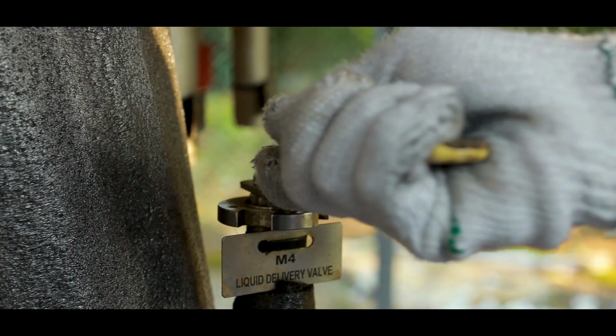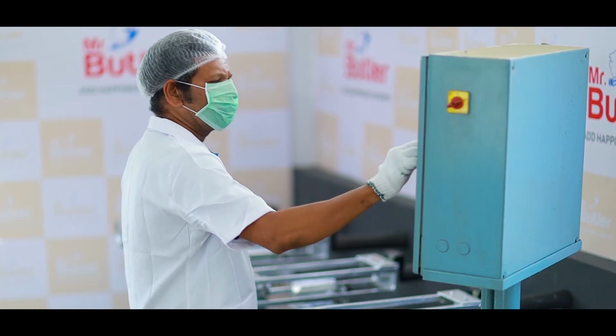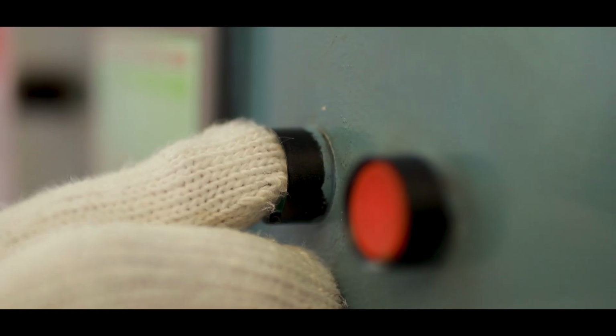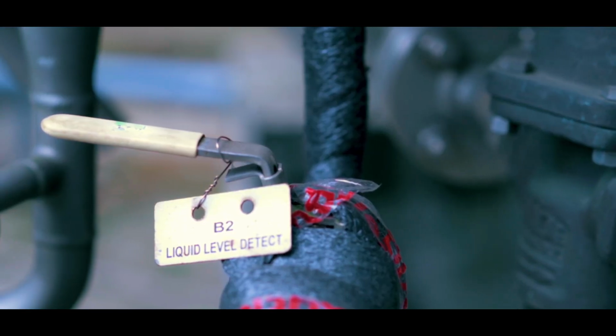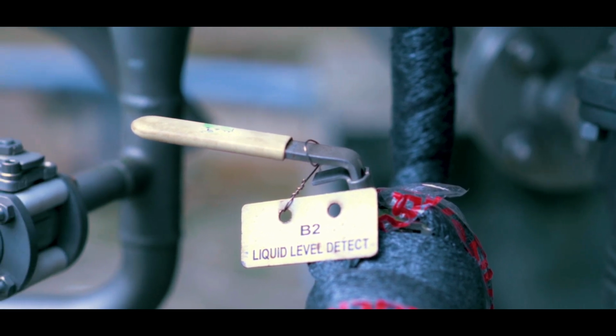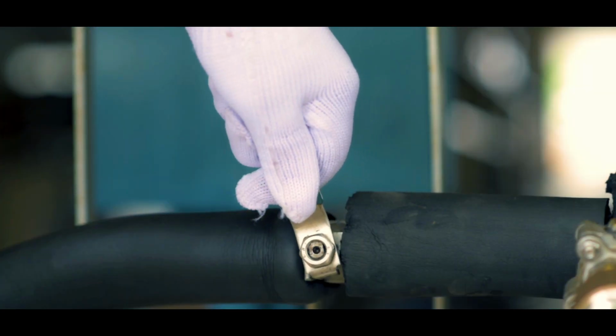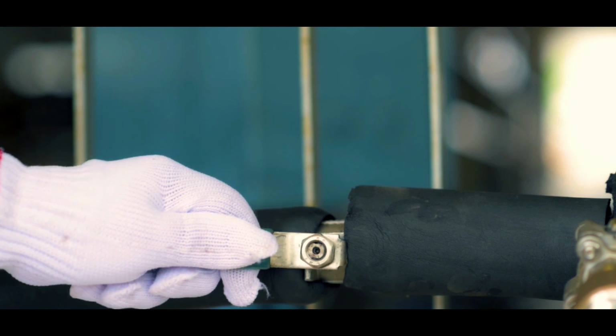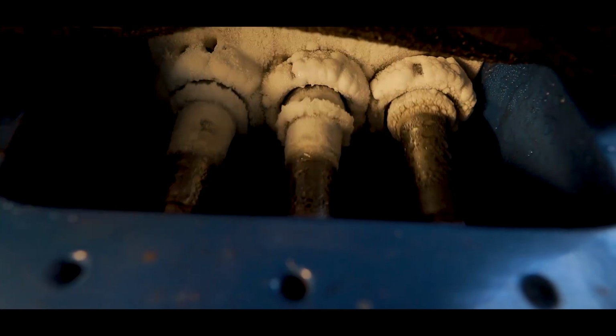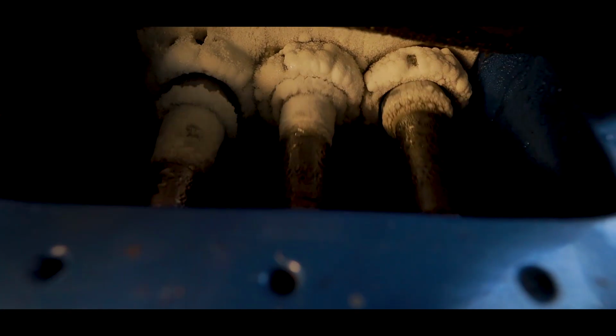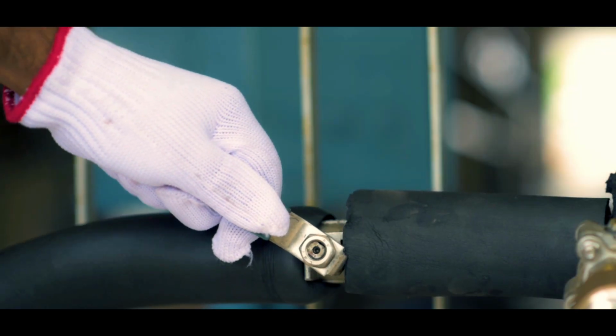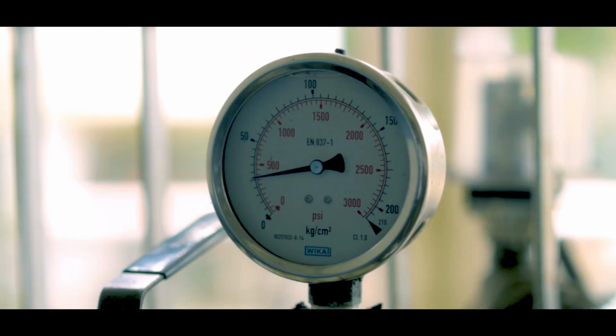First, open the input valve on the tank. Now, start the pump. After that, open the return valve on the tank and then open the bypass valve in the line. Now, the cool cycle starts. Run it for 5 minutes and then close the bypass valve. Pressure will increase in the pipeline, which you can see on the pressure gauge.